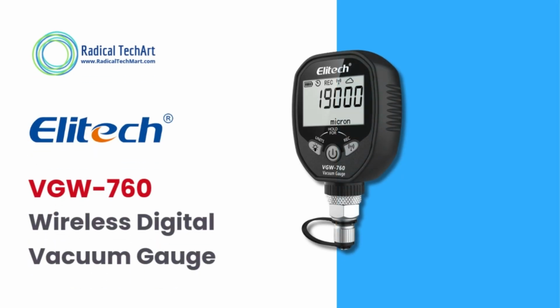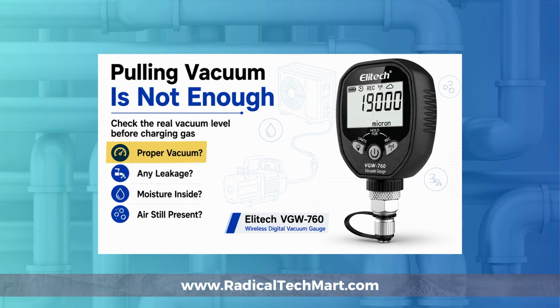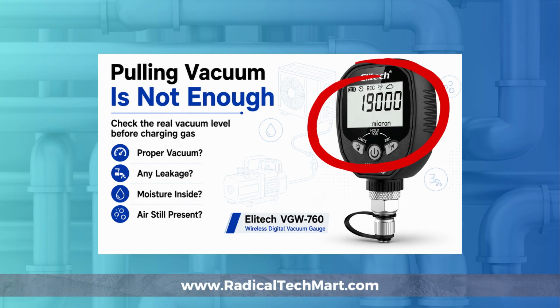In HVAC and refrigeration work, pulling vacuum is not enough. The real question is: is the system properly vacuumed? Is there any leakage? Is moisture or air still inside the system? If we only guess by the vacuum pump sound, we may make a wrong decision. That is why a digital vacuum gauge is important.